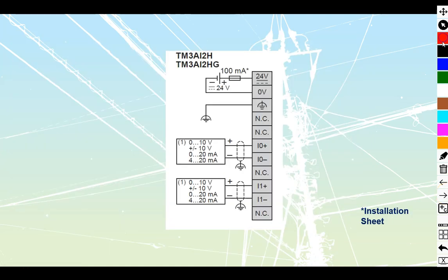The data sheet shows the wiring for it. We're going to start by taking a look at our power supply. It shows that we need to use an external power supply. That external power supply has fusing. We apply positive to the 24 volts, our negative to the zero volts. And we also apply this down to ground. That symbol on top is a protected earth ground. The reason we have that is because we're also going to take a look at these shields in our cables that we want connected to the same one.